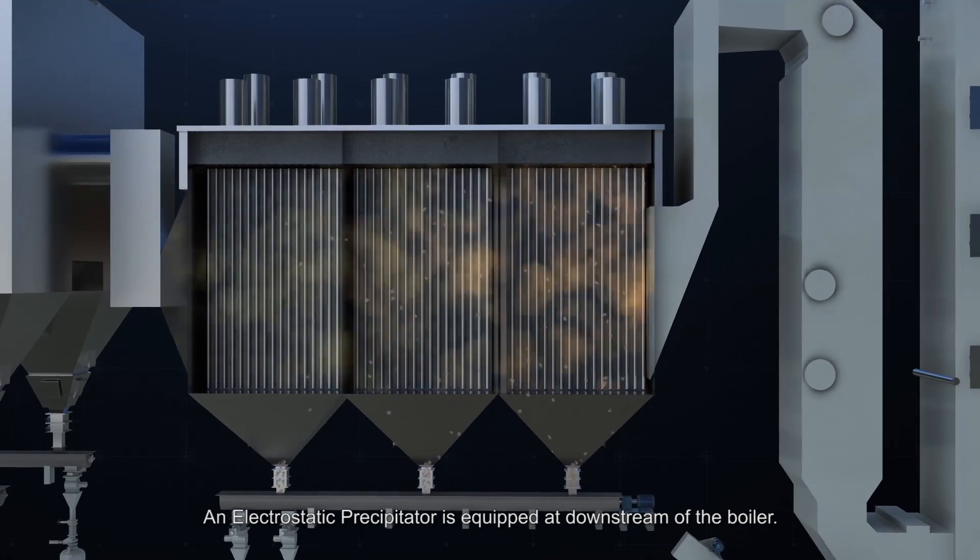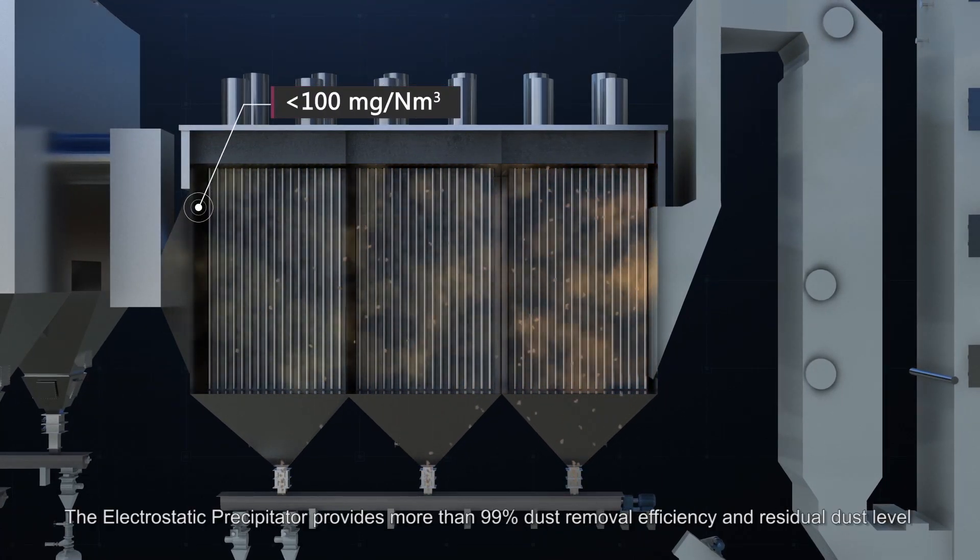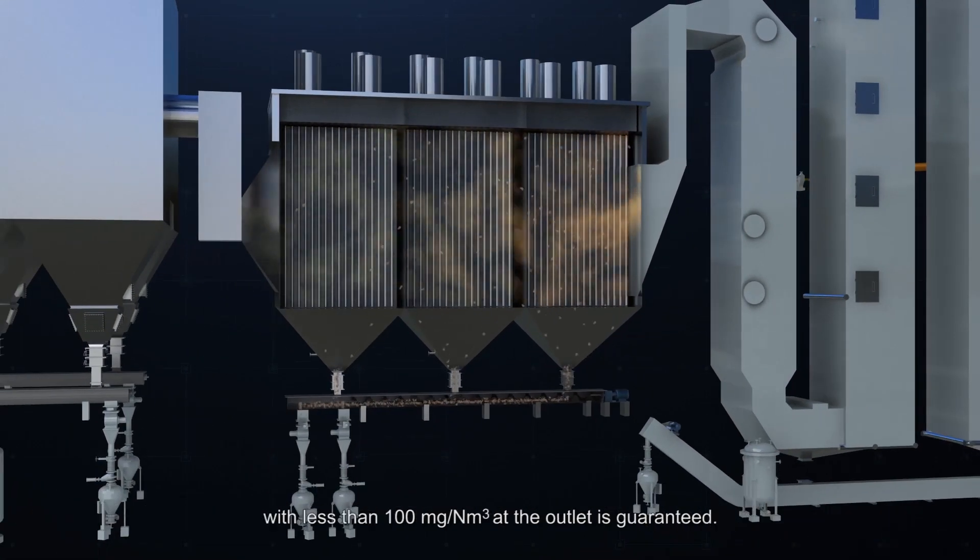An electrostatic precipitator is equipped at downstream of the boiler. The electrostatic precipitator provides more than 99% dust removal efficiency and residual dust level with less than 100 mg per normal cubic meter at the outlet is guaranteed.